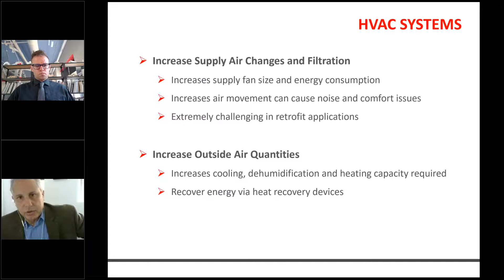On the filtration side, there are different levels of filtration. Each is most effective for removing a specific particle size. So the MERV 8 filtration basically removes the larger dust particles, pollen, spores. This is the minimum you should have in most buildings, your 2-inch filters you typically see. MERV 13 gets the next level down, your bacteria, smoke, and fine dust, and is difficult to retrofit after the fact. Again, those tend to be 12 inches or more deep.